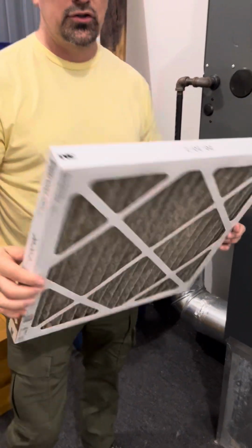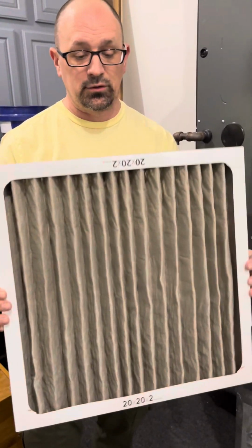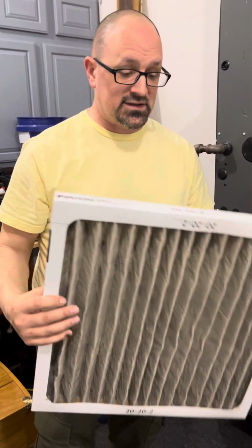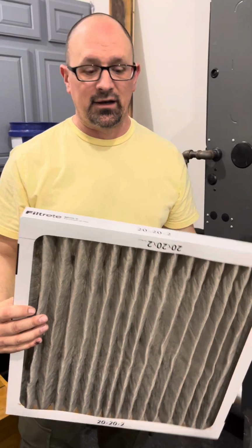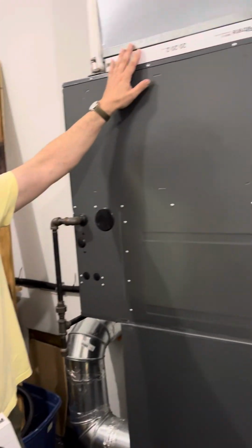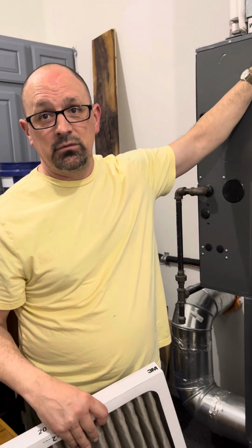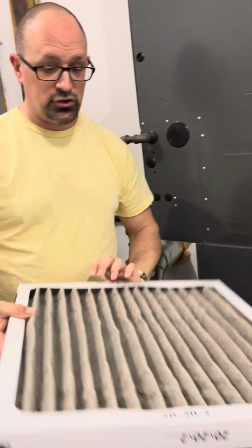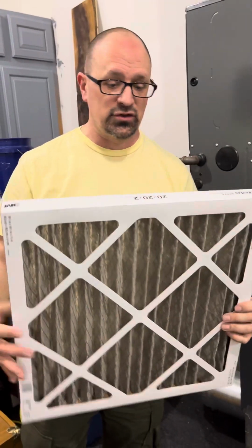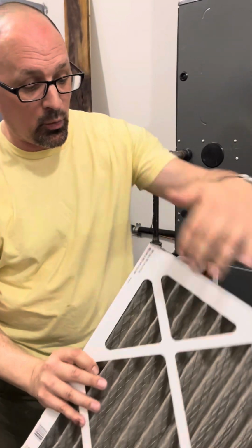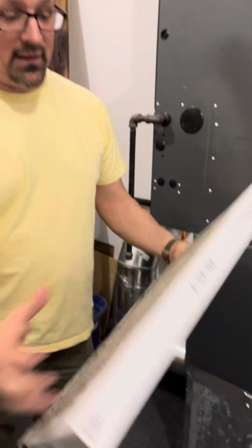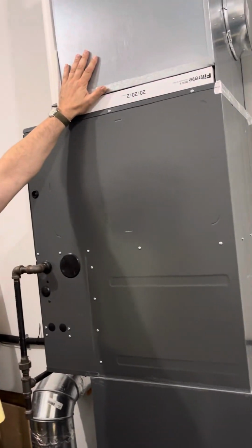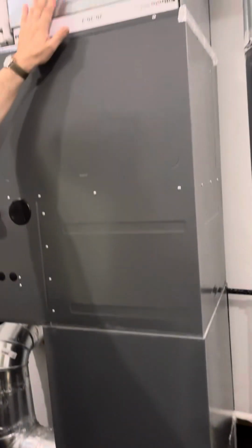If you go to change a filter after 3 months and it looks like this, you're going to want to check your system because something is a little bit too dirty in it. If after 6 months you go to change it out and the filter looks brand new, something's wrong with your system. After about 6 months, this is what your filter should look like. On average, it's filtering the air. You don't want to see this collapsed in. If it's collapsed in, it's not filtering anything. So the biggest thing, again, return air, supply air, the filter goes on the return side.